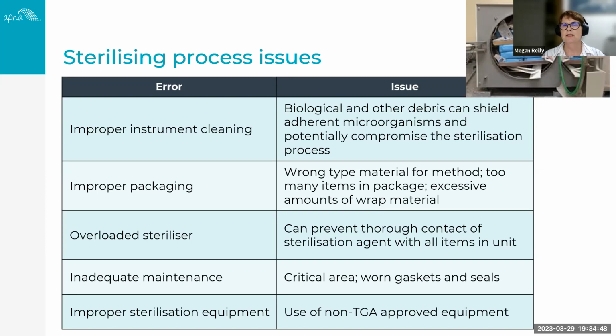gaskets wear. So these are all part of the checking procedures, the documented procedures, and they should be in accordance with the maintenance requirements that are set out in your steriliser manufacturer's instructions for use. And as I referred to earlier, making sure that you do have appropriate sterilisation equipment. In fact, all of your reprocessing equipment needs to be TGA approved.